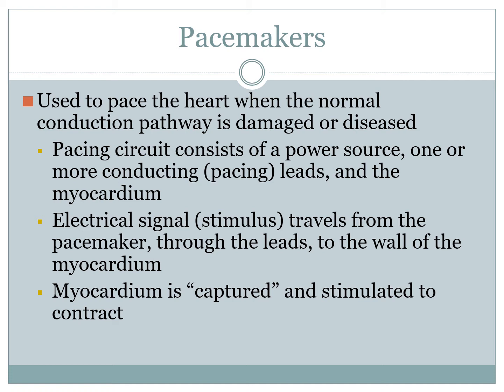The pacing circuit consists of the power source, always called the pulse generator, and the leads, could be one or more, and then finally the third element is the myocardium itself, the heart muscle. The electrical stimulus has to travel from the pacemaker through the leads to the wall of the myocardium. Now, at the end of the leads is a small hook or anchor, which is not shown on the previous slides in the diagram, but in reality there is a little hook there, and that hook needs to get buried within the myocardial tissue.